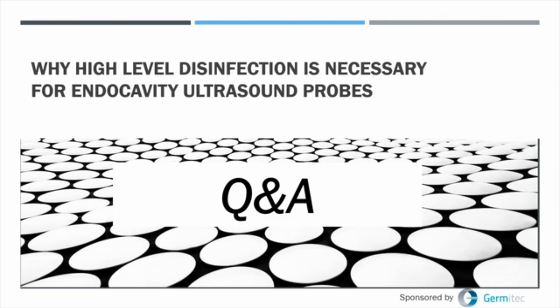Okay, next question. What is the correct method to clean and wipe the probe? Any specific way of cleaning? So here I cannot give you absolutely specific guidance on cleaning. I'll give you some general guidance. You need to look at, for your high-level disinfection method and the exact probe, what the manufacturers recommend for the cleaning method. That is, what type of specific wipe they use, or is it an immersion into water, or is it put into running water?